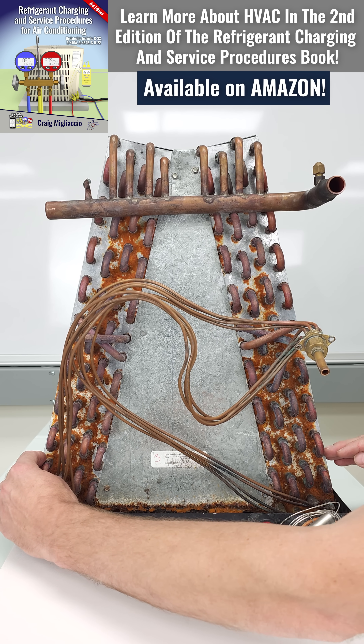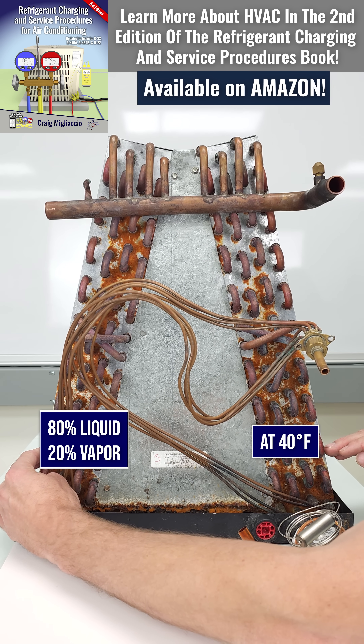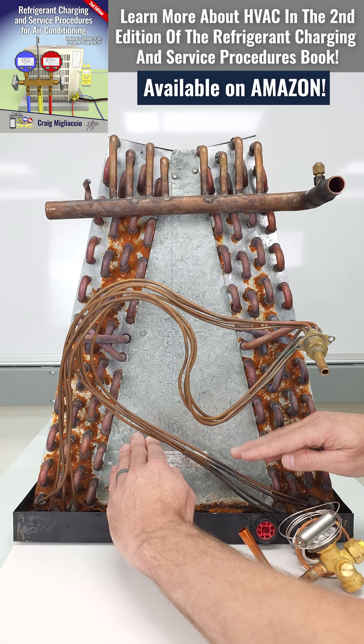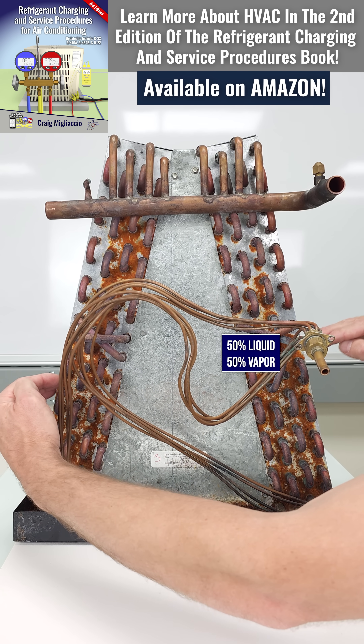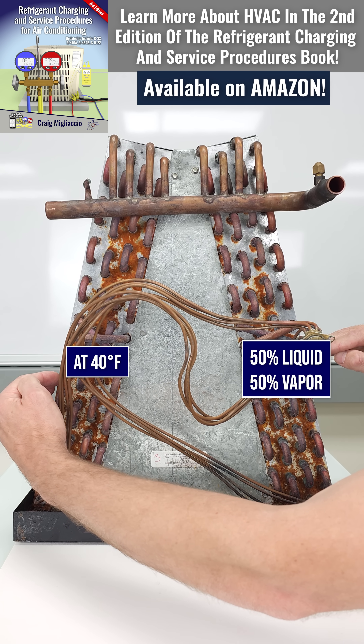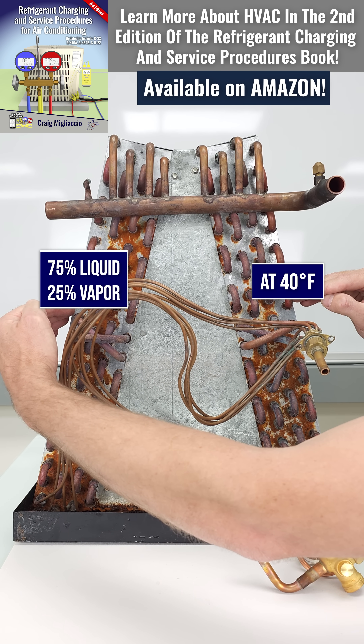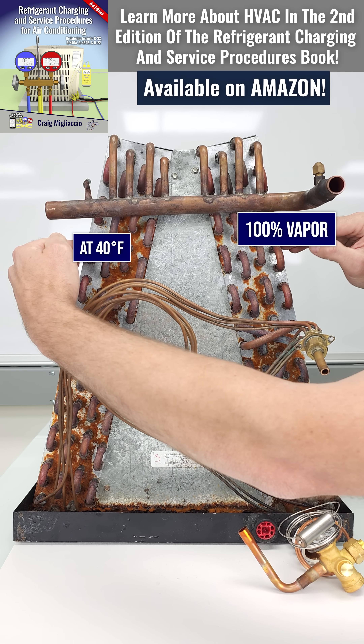At this point you have maybe 80% liquid and 20% flash gas at about 40 degrees. As the refrigerant flows through the coil and absorbs heat from the air crossing over the coil, it undergoes a phase change — maybe now 50% liquid and 50% vapor, still at 40 degrees. Then maybe 75% liquid and 25% vapor, and then 100% vapor, still at 40 degrees.